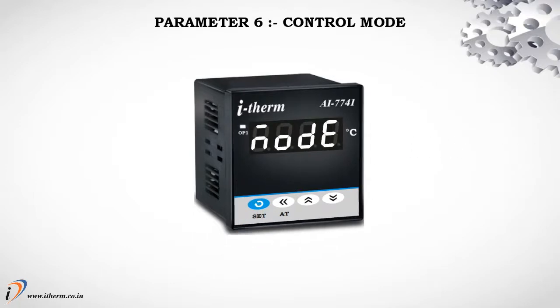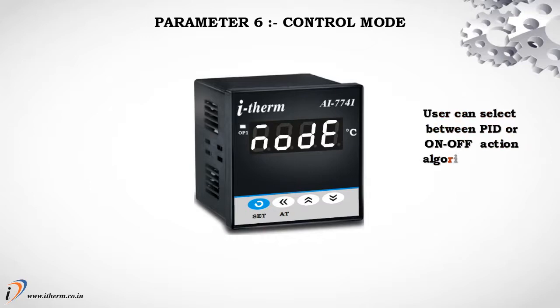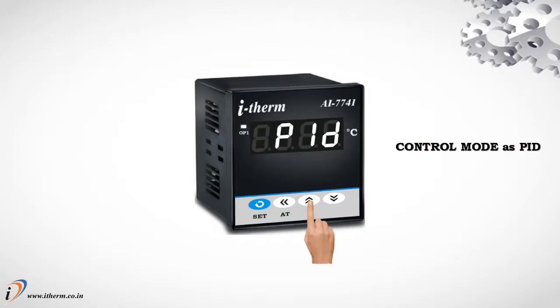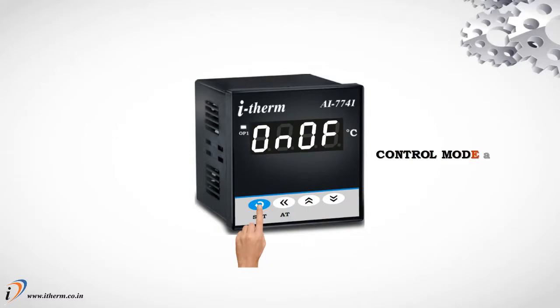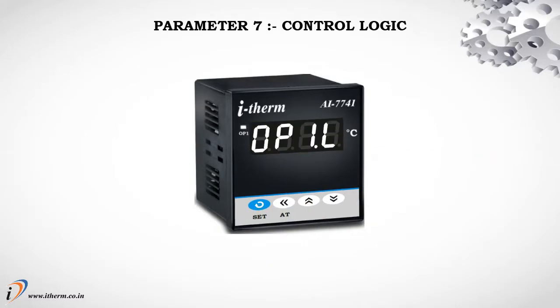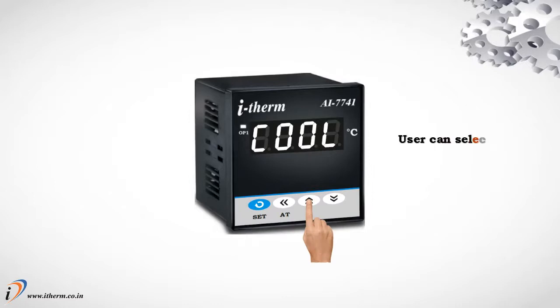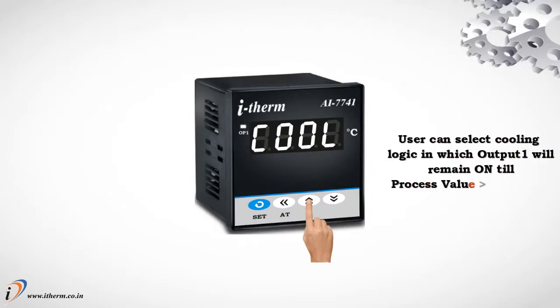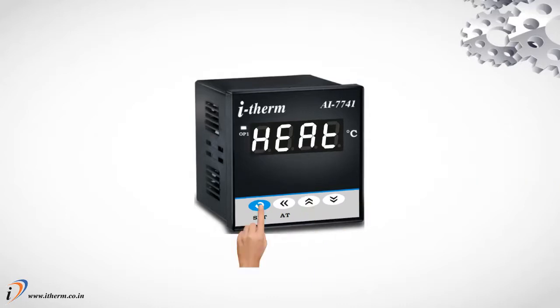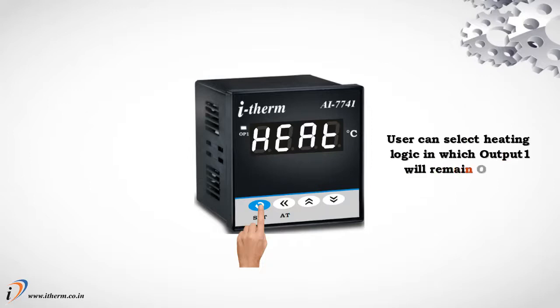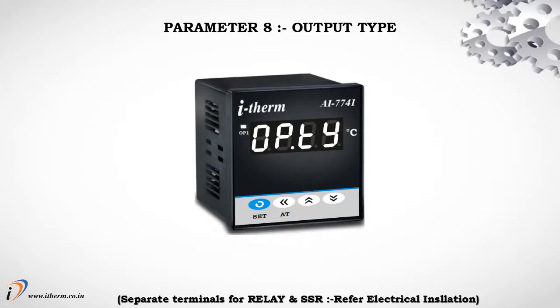Parameter 6. Control mode. User can select between PID or on-off action algorithm to be adopted for output. Control mode as PID. Control mode as on-off. Parameter 7. Control logic. User can select cooling logic in which output 1 will remain on till process value is more than set point. User can select heating logic in which output 1 will remain on till process value is less than set point.